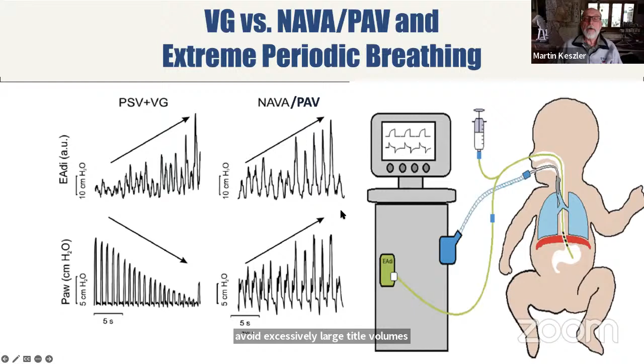Volume guarantee was designed for premature infants with irregular and immature respiratory control. So when the baby doesn't breathe much or doesn't breathe at all, the ventilator generates more pressure. When the baby generates vigorous inspiratory effort, as they do when the baby is stimulated or handled, the machine backs off quickly to avoid excessively large tidal volumes.